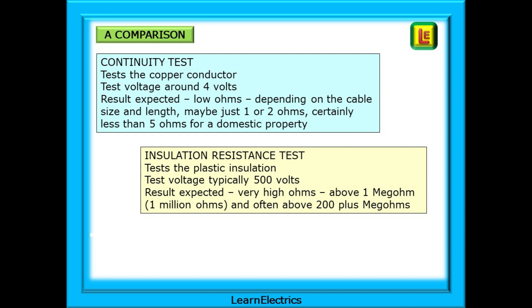The continuity test is checking the copper conductor with a test voltage of around 4 volts. The result expected is a low ohms result and depending on the cable size and length it is perhaps just one or two ohms of resistance, and certainly less than five ohms for a domestic property. Knowing what values to expect will become familiar to you with practice.